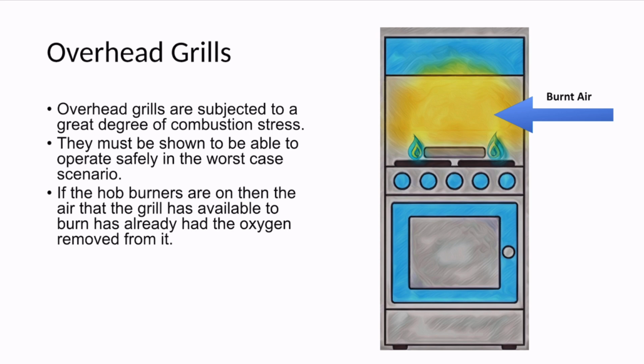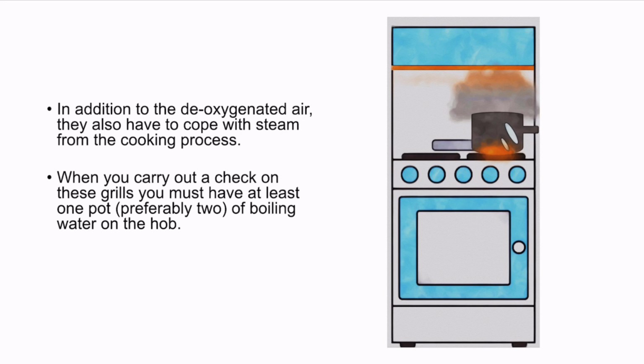Remember that if the hob burners are on, then the air that the grill above it has access to has already been burned, and it's had the oxygen removed from it. So already it's struggling because the air that's around it no longer has any oxygen in it. In addition to the deoxygenated air, they also have to cope with steam and grease and goodness knows what else going up into them if you're doing something on the hob itself. So in your assessment, when you carry out a check on these grills, you must have at least one pot, preferably two. If you can, always use two, of boiling water on the hob. So you put the pans on the hob, you heat them up, you get them boiling, then you do your test.